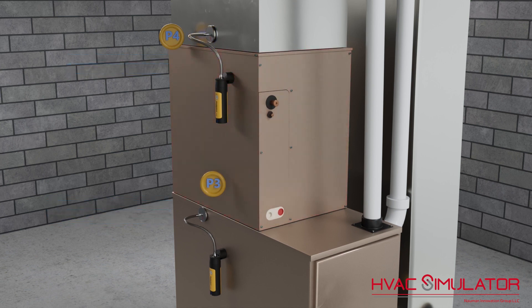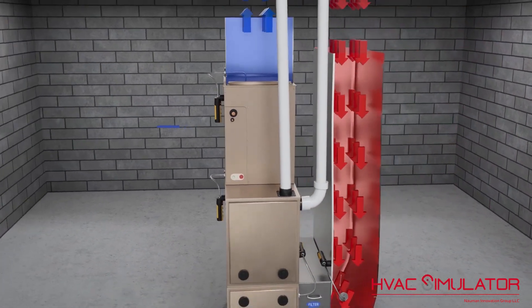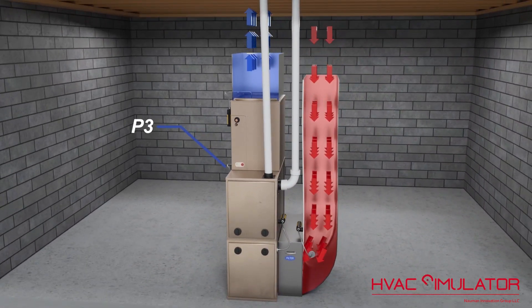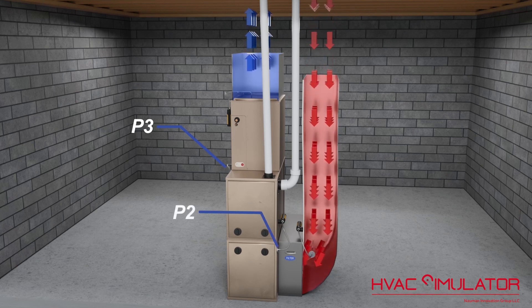Total external static pressure is the pressure measured external to the equipment. It's the difference between the total pressure on the negative side of the system and the total pressure on the supply side. Or, external static pressure is the difference between P3 and P2, where P3 is the greatest positive pressure and P2 is the greatest negative pressure.